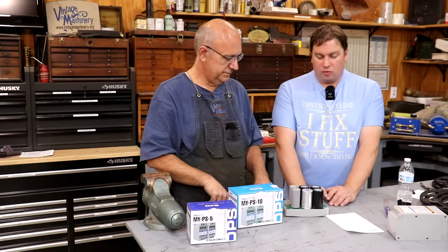You'll also notice how labored the startup was. With the rotary phase converter, it starts up pretty quickly. With these little units and their capacitive-assist start, it doesn't have the same starting torque and it's not going to start under the same load. If you're starting something under load, this is probably not something you ever want to do. Starting loads draw much higher current — up to 10 times inrush current — and you're passing all that current through this device, which is probably not rated for it.